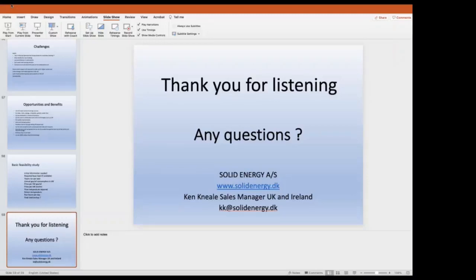A question from Adam: in regards to retrofitting in a current single glazed commercial property with a gas boiler, wet heating system, is the best way of retrofitting a heat pump to maintain the current gas boiler and install a heat pump with an immersion heater to offset carbon emissions and improve efficiency? The best way is to go down that bivalent route, heat pump in to provide the base loads, probably for the domestic hot water as well, if needed. Leave the gas in just to top up, and you can reduce the carbon footprint by up to 90%.